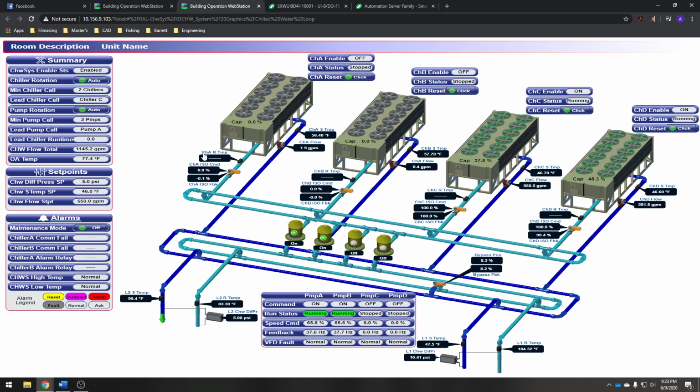Let's talk about the command valves, the isolation valves. That's another component that we added. Previously, if you had a chiller that was off, the remaining chillers, just due to the way the valving was on the roof, were actually flowing water through the system. So there was water moving through these pipes without this chiller being on. That adds extra head pressure and loss of flow, which is why we think you could only run a certain configuration of chillers for the system to actually cool properly.